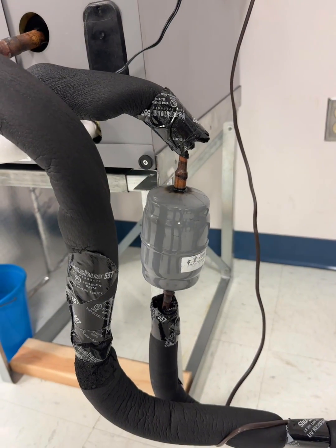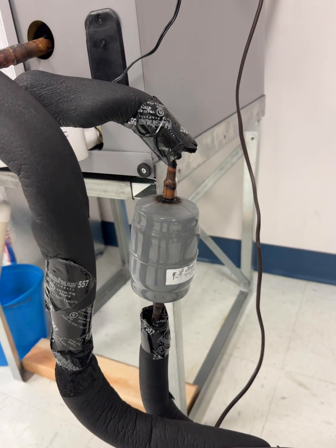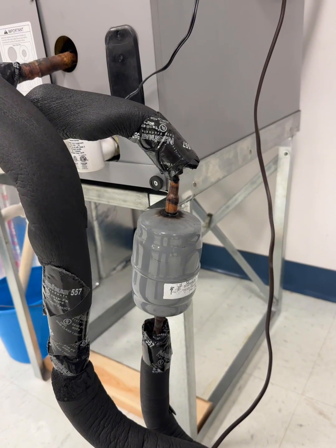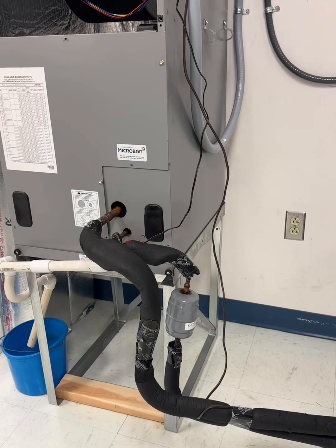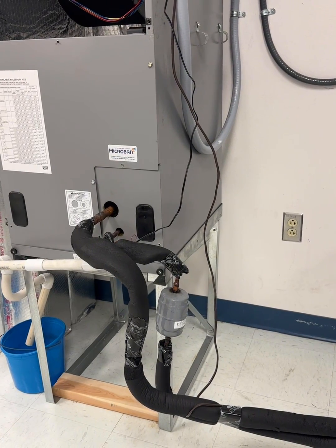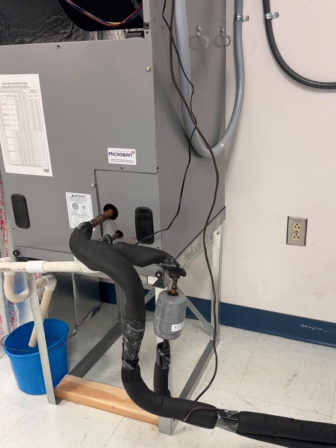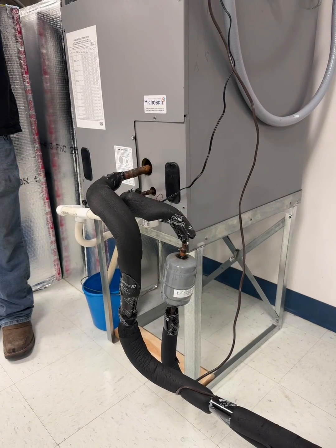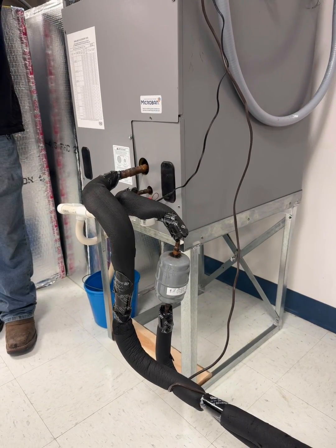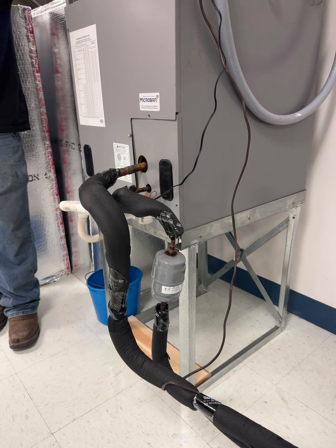The function of a filter dryer. The dryer contains a material that absorbs moisture from the refrigerant. Moisture in the system can freeze at the metering device, forming an ice blockage, or react with oil and refrigerant to form acids that damage the compressor.